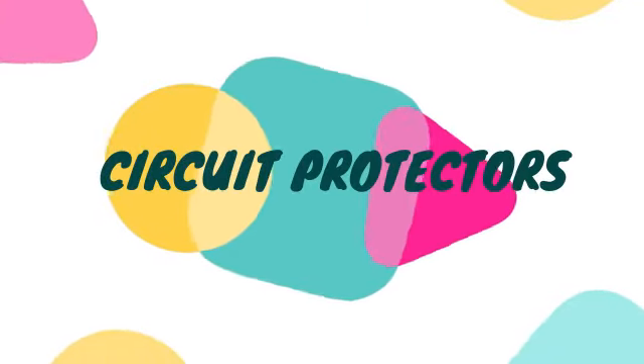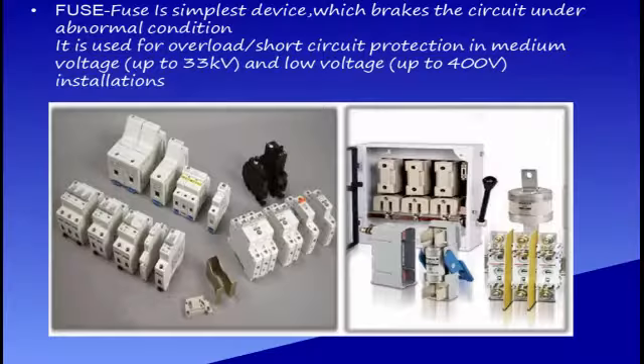Today we're going to discuss circuit protectors, and one of these is the fuse. It is the simplest device which breaks the circuit under abnormal condition. It is used for overload and short circuit protection in medium voltage installations up to 33 kilovolts and low voltage installations up to 400 volts.